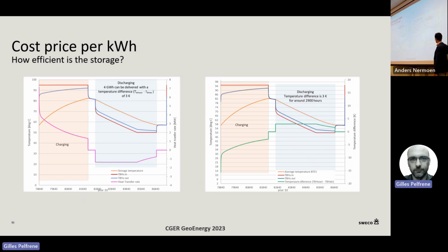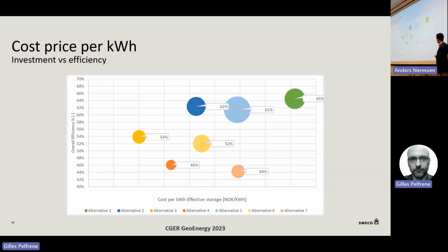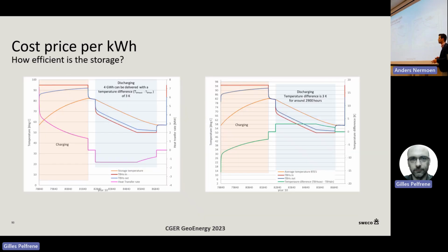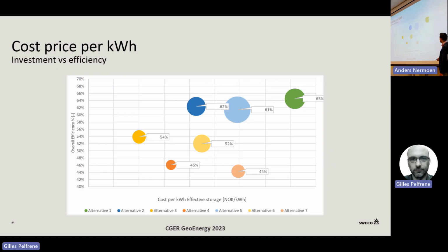This is how it looks in terms of temperature difference. We operate with about 6-7 degrees in the beginning, decreasing to about 3 degrees - that's the in and out temperature. This is the storage temperature again, going down to about 58 degrees. It's designed to deliver about 1.5 megawatt throughout the winter until we reach a plateau, around February or beginning of March, when we can't supply as much energy because the temperature gets too low in the storage.